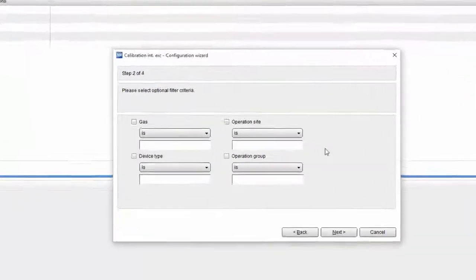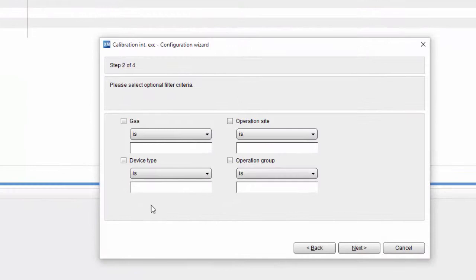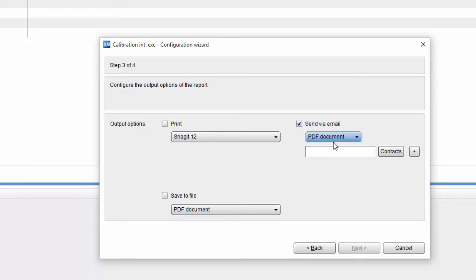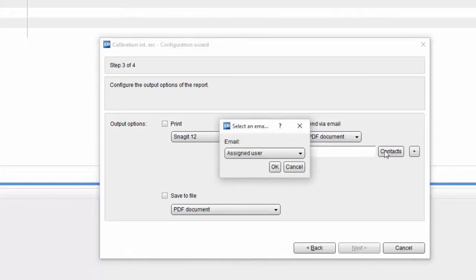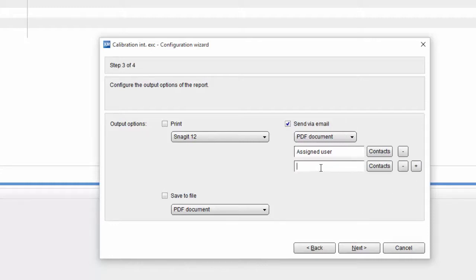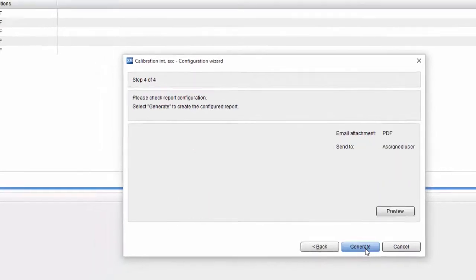Here you can also define pre-warnings and filters and select how the report should be created. Event schedules can also be emailed to the assigned user. This means that the user to whom the instrument is assigned will be informed that the instrument needs to be calibrated, either with a pre-warning or directly when the calibration becomes overdue. The user's email address, of course, needs to be stored in the user management table for this.